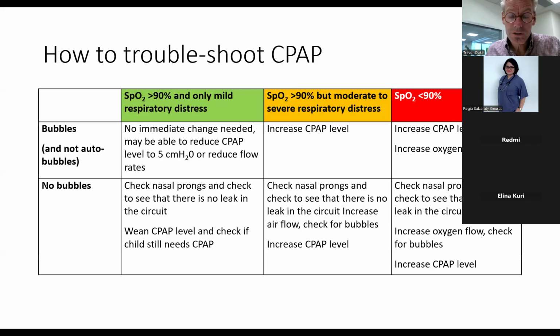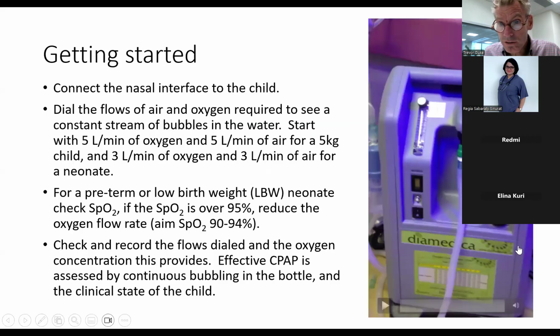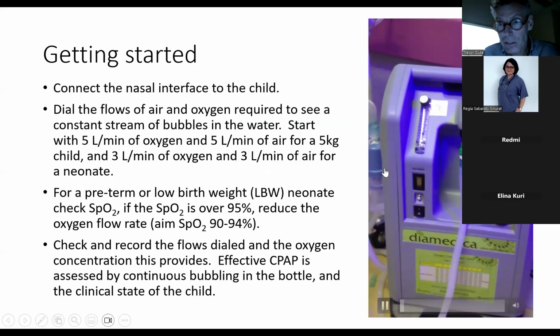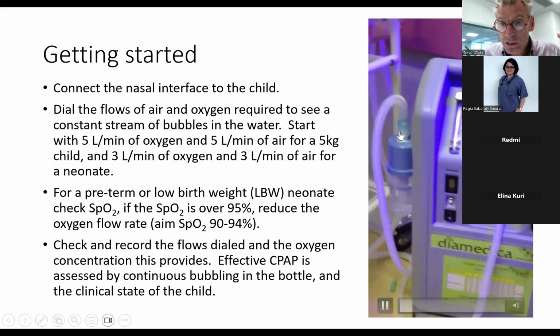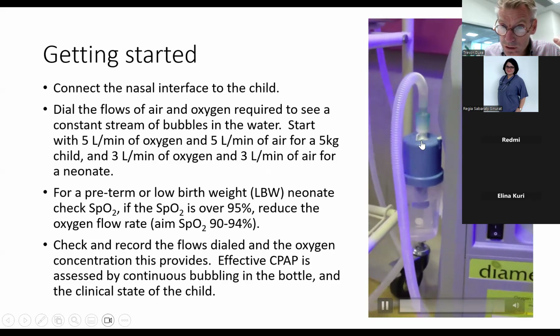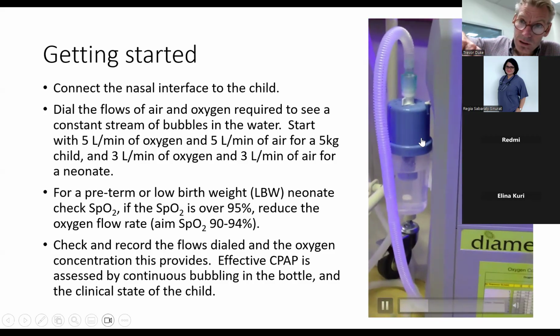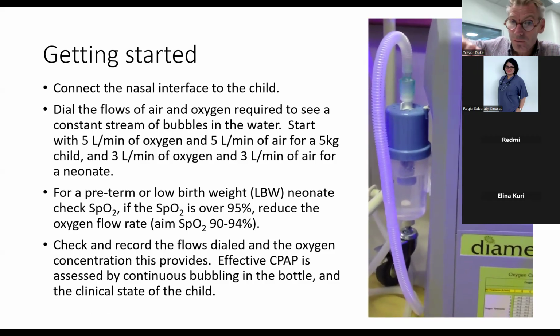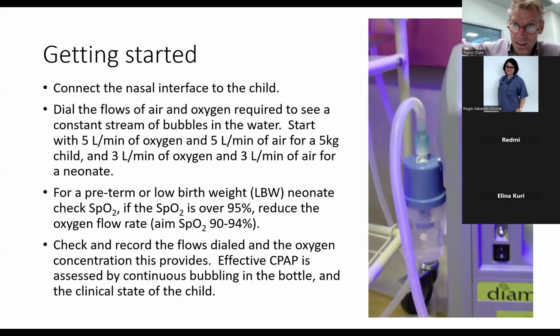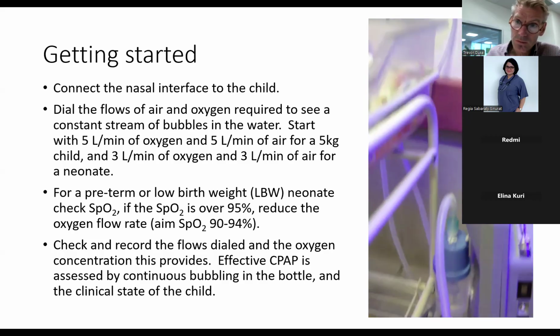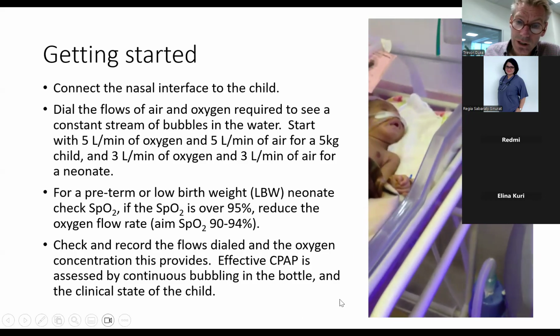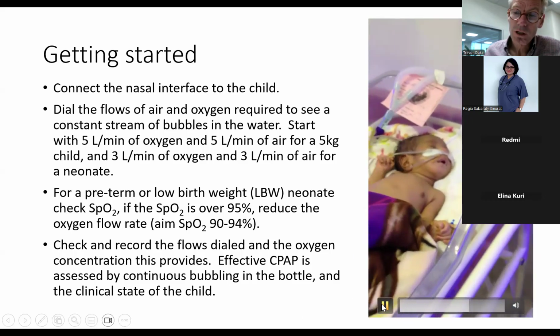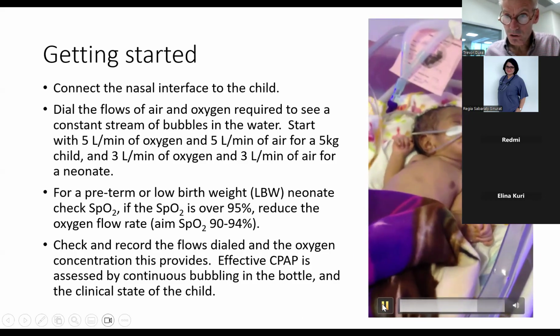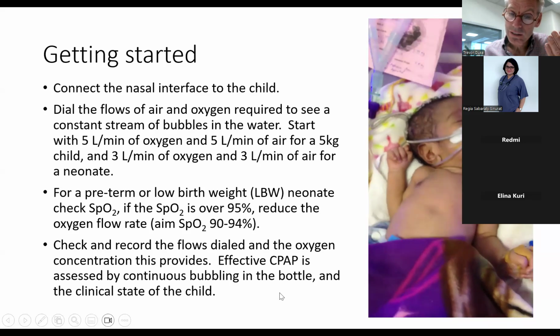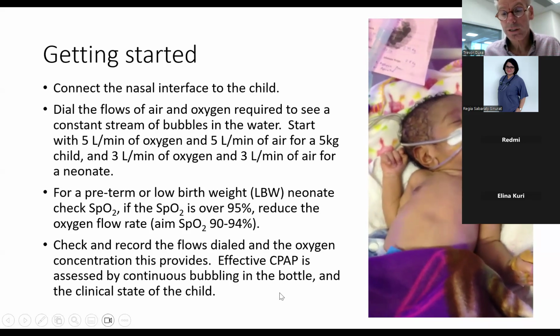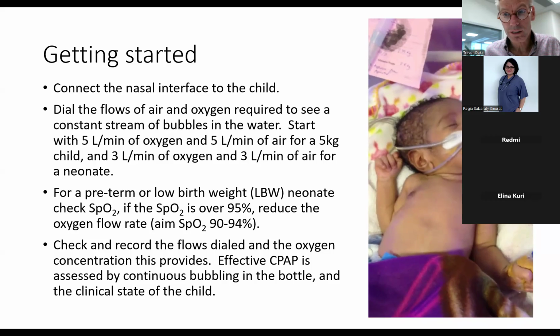And you titrate, I should just explain, you're titrating the CPAP level. I'll show you this. You're titrating the CPAP level using a dial on the bottle here. And the bottle dial can be dialed up to 5, 7, 10, or down to 3, or whatever you want. Right. So that's where you dial the CPAP level, and you dial the oxygen level through the oxygen flow meter, and you dial the air level through the air gas flow meter.